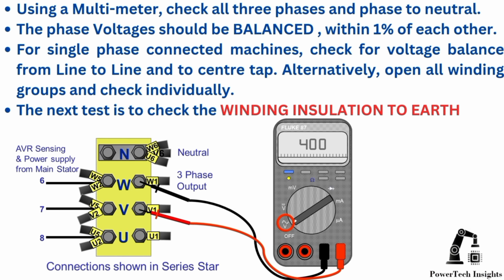Using a multimeter, check all 3 phases and phase to neutral. The phase voltages should be balanced within 1% of each other. For single-phase connected machines, check for voltage balance from line to line and to center tap. Alternatively, open all winding groups and check individually.